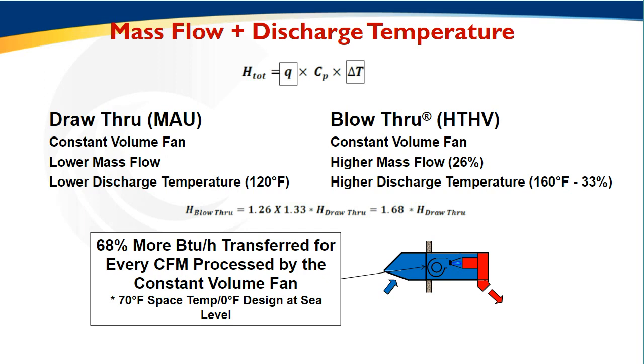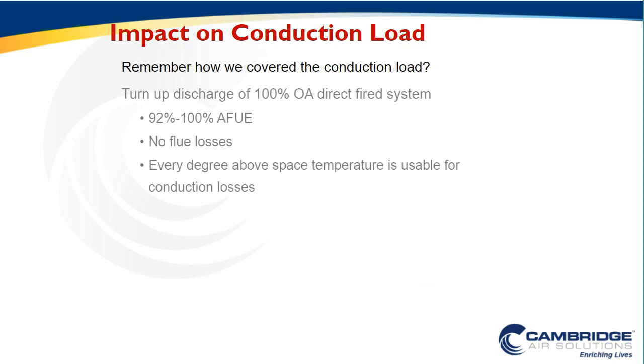But really, when we talk about high-performing warehouses and fulfillment centers, we want to talk about how does this building allow for lower energy usage and how can we use less energy to heat our conductive loads. So let's go back to our conductive load equation we said earlier. How do we cover the conductive loads? Well, both the makeup air system and the HTHV systems are going to heat the conductive load the same way. Whatever discharge temperature, whatever temperature I have above space temperature is really the only usable heat that I have to heat my conductive loads. They're both going to be 100% efficient.